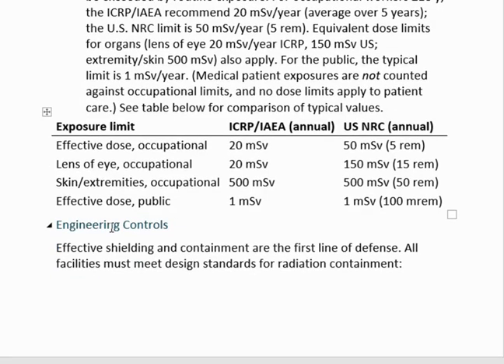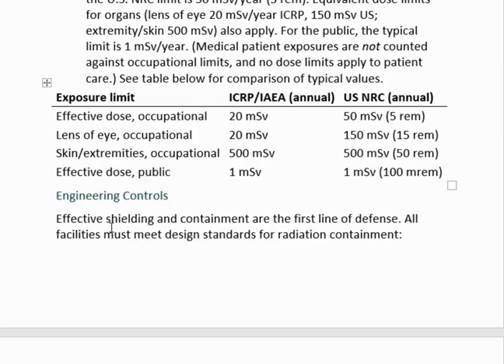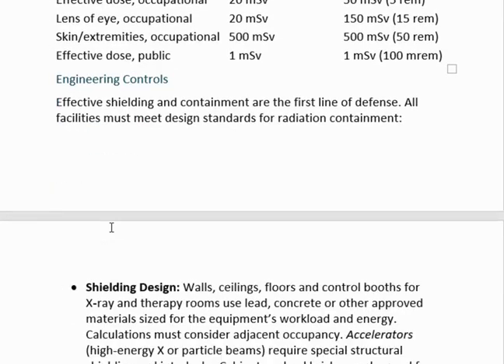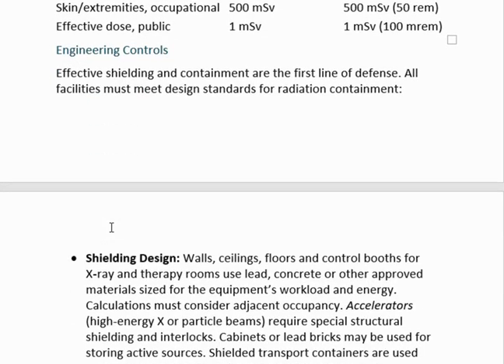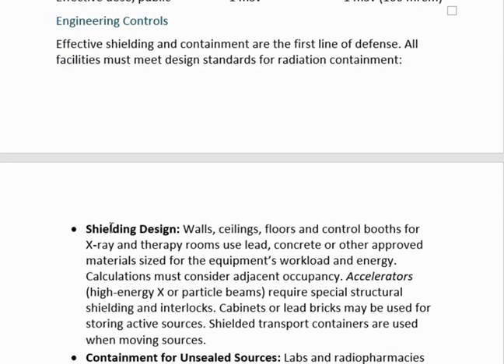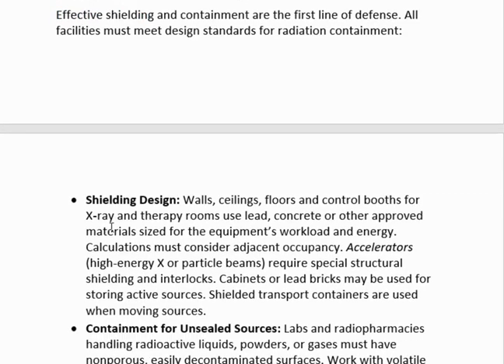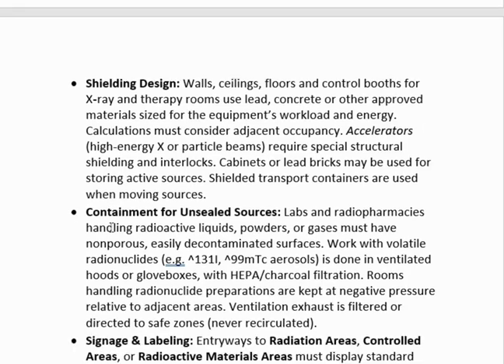Engineering controls. Effective shielding and containment are the first line of defense. All facilities must meet design standards for radiation containment. Shielding design. Walls, ceilings, floors, and control booths for X-ray and therapy rooms use lead, concrete, or other approved materials sized for the equipment's workload and energy. Calculations must consider adjacent occupancy.